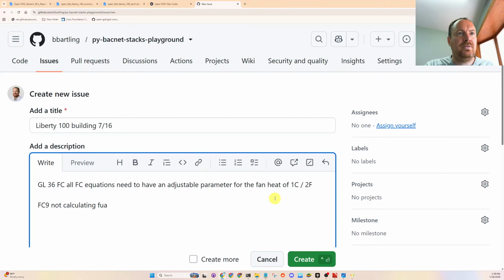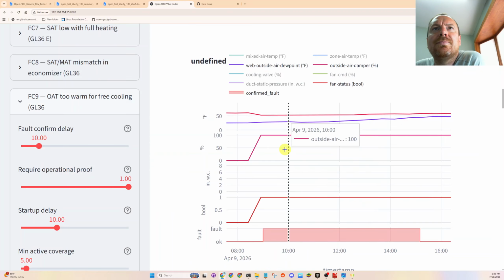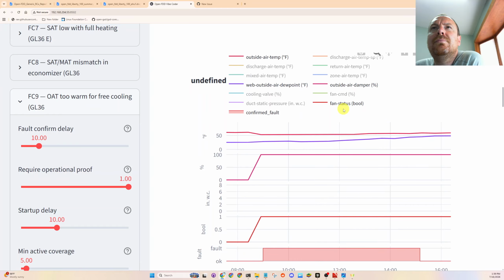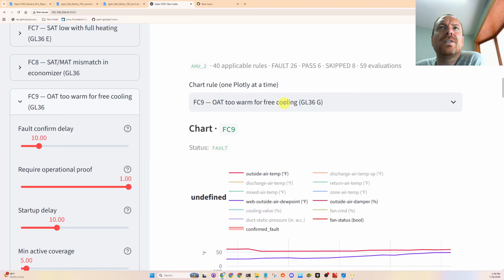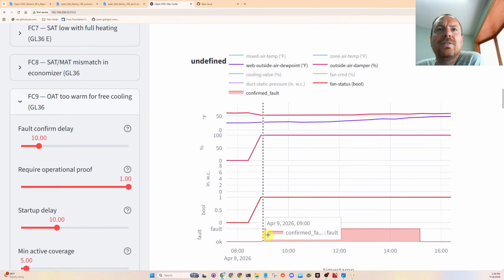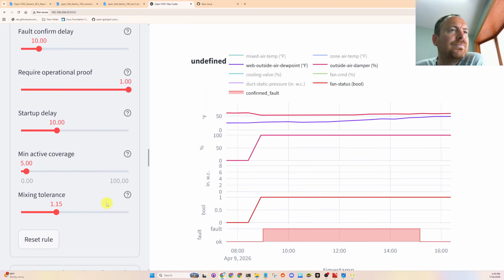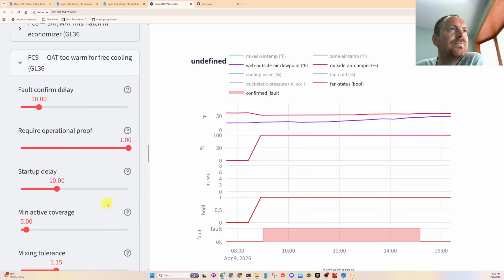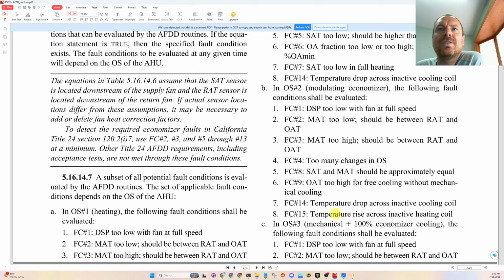Calculating faults. Data was confirmed. It's proper. So okay, I will look into this, because this is exactly what we would want. Let me just see. We're definitely on fault condition 9, confirmed fault. Why would this be flagging a fault? Let's just look at Guideline 36 for outside air temps too high for free cooling without mechanical cooling.